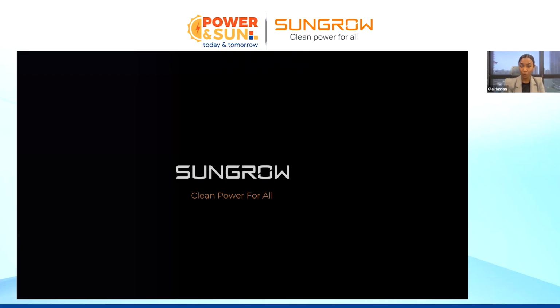Okay, so actually both will work because both of them have the same objective. Both of them can work in on-grid, off-grid, and switching between on-grid and off-grid. But if, for example, there's an existing PV system and later you want to add a diesel generator or BESS, of course the AC coupled is better. If the system is big in capacity as well, because now the DC coupled is up to 3 megawatt, and maybe your system is bigger than 3 megawatt, then the AC coupled will be better as well. But if it's a new system and it's small, perhaps 125 kilowatt, 250, 500, 600 kilowatt, about that capacity, the DC coupled of course will be better. So it depends on my application and on my system capacity itself. But both of them can work with diesel generators, with off-grid, with energy storage, on-grid, and seamless switching.